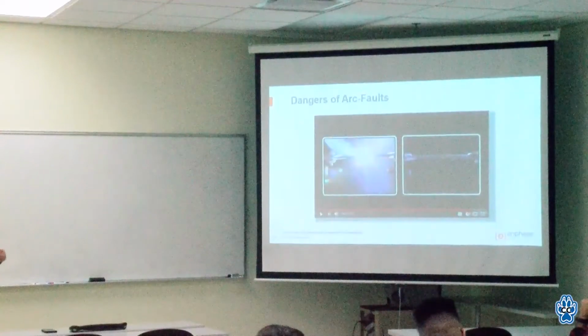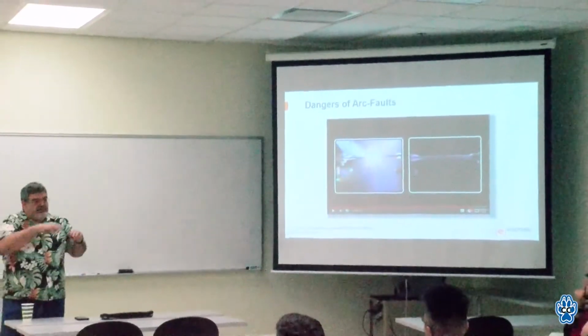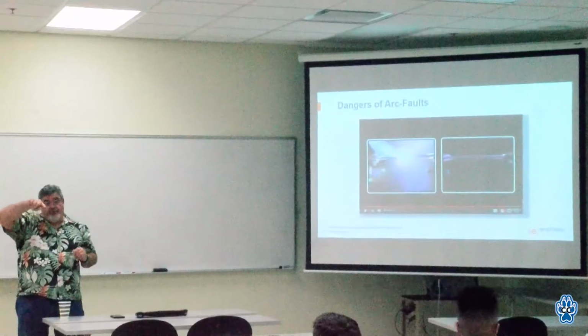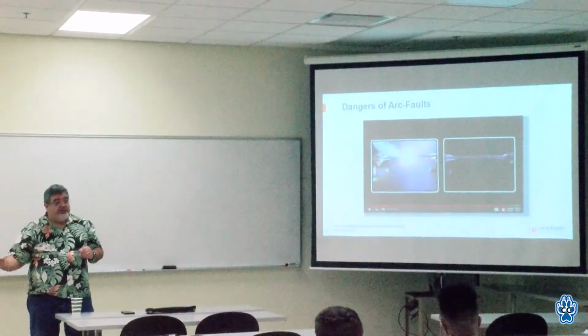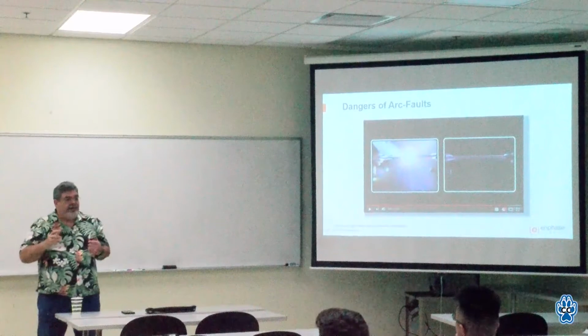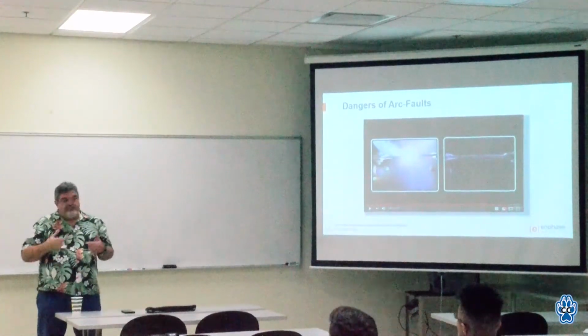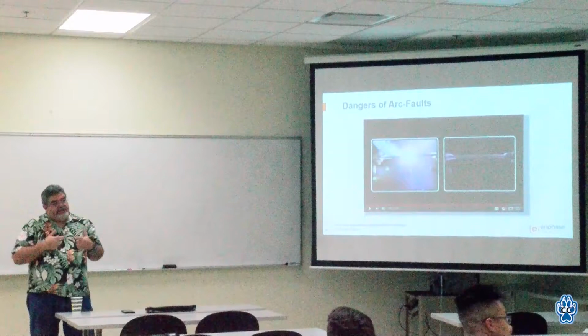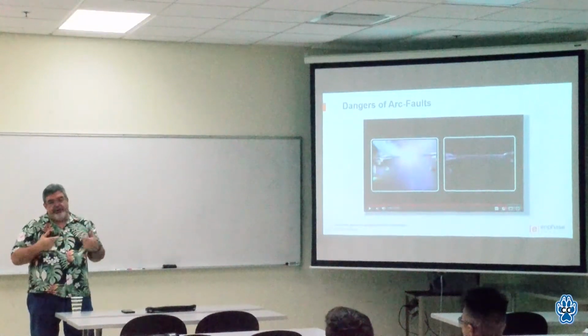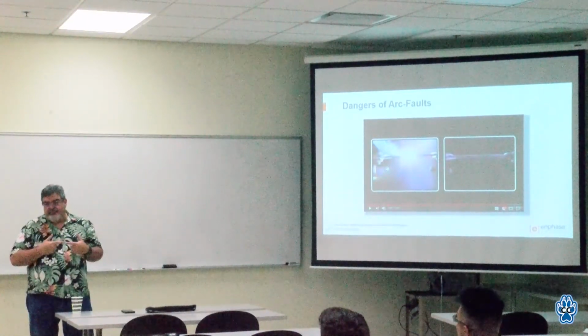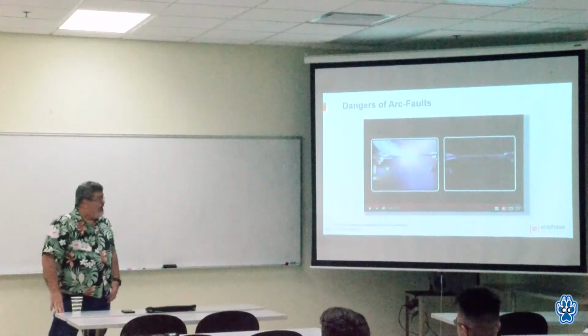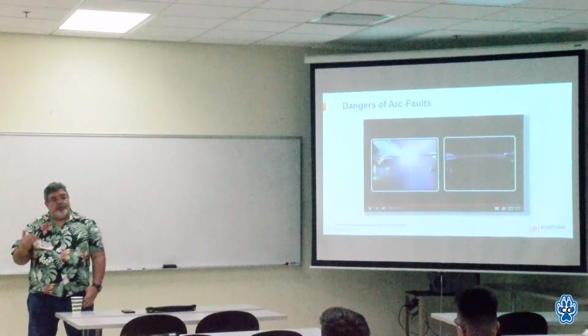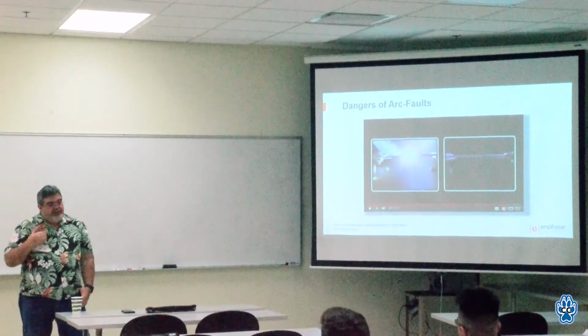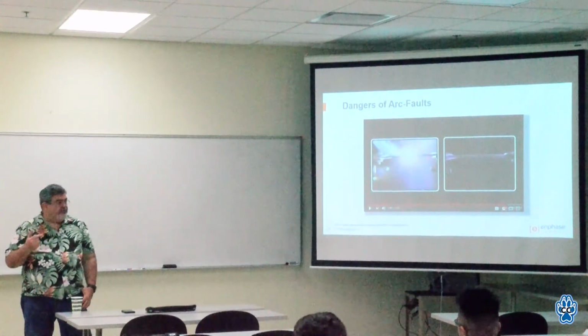With AC power, you oscillate through a sine wave. So say you start at 0, you go negative, you go through 0 again, you go positive, you go back through 0. So you're always going through 0 crossings, and that helps extinguish the arc because you can't get an arc at 0 volts. But with DC, the voltage stays constant, and that's why that arc continues to propagate like that, and it just continues on and on and on. So they're inherently more dangerous. They present a higher risk of fire in a situation like that.